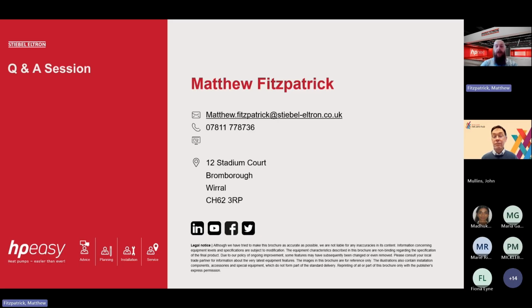Yes, so there was a new change in regulation regarding ventilation inside properties. It's all to do with mold, mildew, and damp. And that has come into play, I think it was last month or a couple of weeks ago. And it means housing associations and private landlords have, I think it's 10 working days to rectify any concerns or reports of mold or mildew appearing in properties, and then a further 5 days to rectify the issue. There are different strategies to be able to control humidity, mold and mildew, and ventilation. There are passive ventilation aspects such as trickle vents, but we need to ensure that the tenant leaves the trickle vents open. There are ventilation aspects such as centralized mechanical ventilation and heat recovery, which can be quite disruptive. And then there are less disruptive paths such as decentralized ventilation.